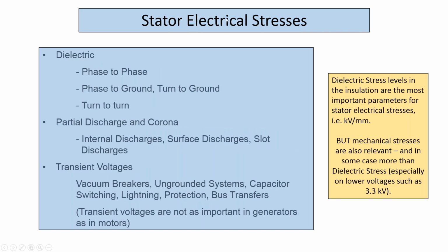Your stator electrical stresses are basically about kilovolts per millimeter. In other words, what is your electric field at various points in your insulation? So you can have an electric field of 10 kV per millimeter in insulation and it won't break down. But if you have 10 kV per millimeter in air, it will break down. And depending on what insulation is involved and what the electric stresses are, you will or won't have partial discharge, that's breakdown in air, or electrical breakdown, but that does not short circuit the entire insulation system.